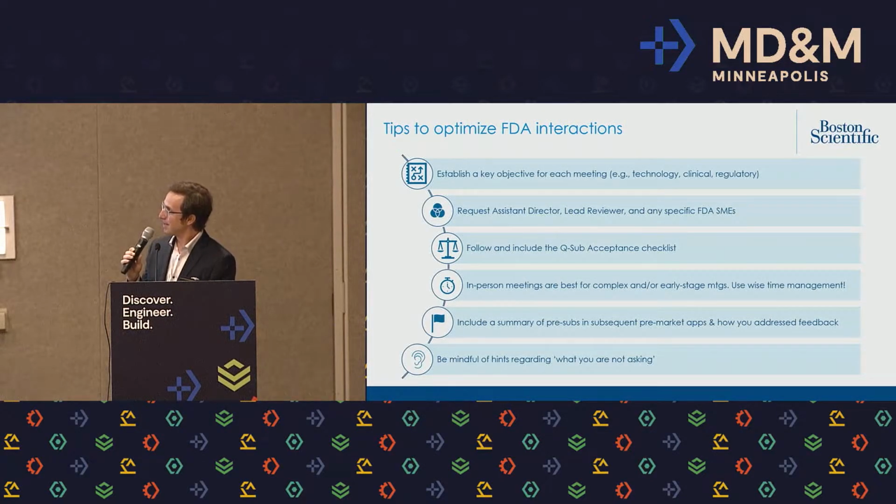And I apologize, this came out kind of small. So a couple tips to optimize these FDA interactions is, first, establish a key objective for each meeting. So we, at our company, will usually go in for an informational meeting to just establish some rapport with the review team, kind of a meet and greet and an introduction to what the technology is. We'll go in for a second pre-submission on the non-clinical aspects, maybe the critical path items from bench testing, or we'll align on biocompatibility or animal testing.